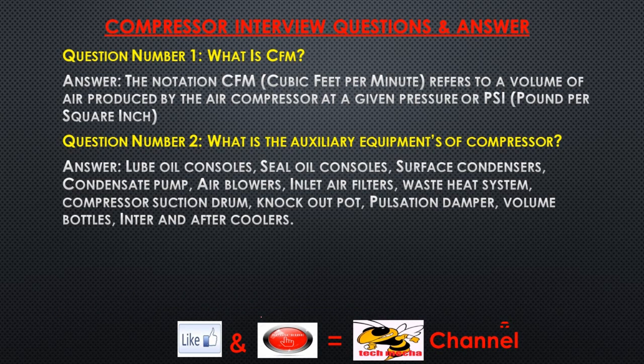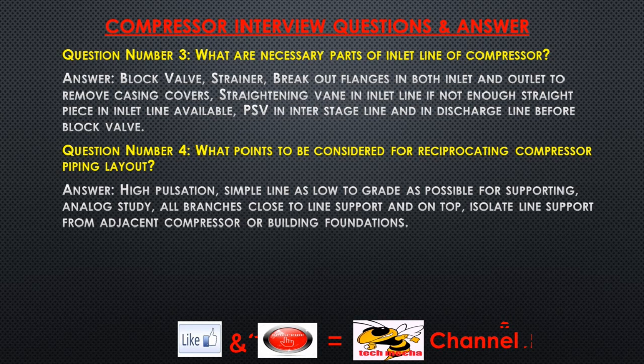Question number 3: What are the necessary parts of the inlet line of a compressor? Answer: Block valve, strainer, breakout flanges in both inlet and outlet to remove casing covers, straightening vane in inlet line if not enough straight piece in inlet line is available, PSV in interstage line and in discharge line before block valve.